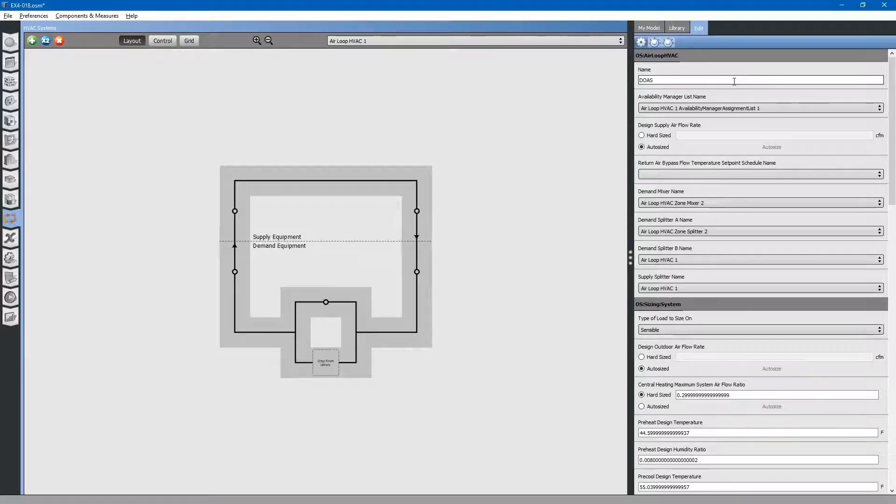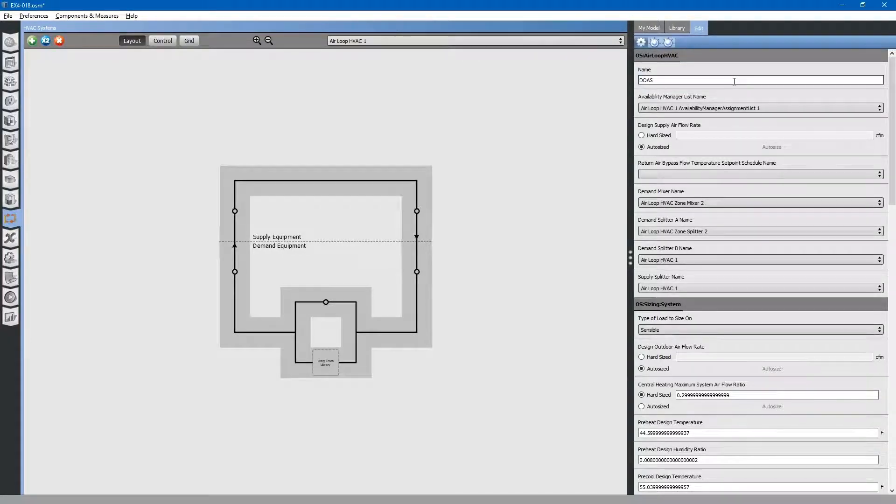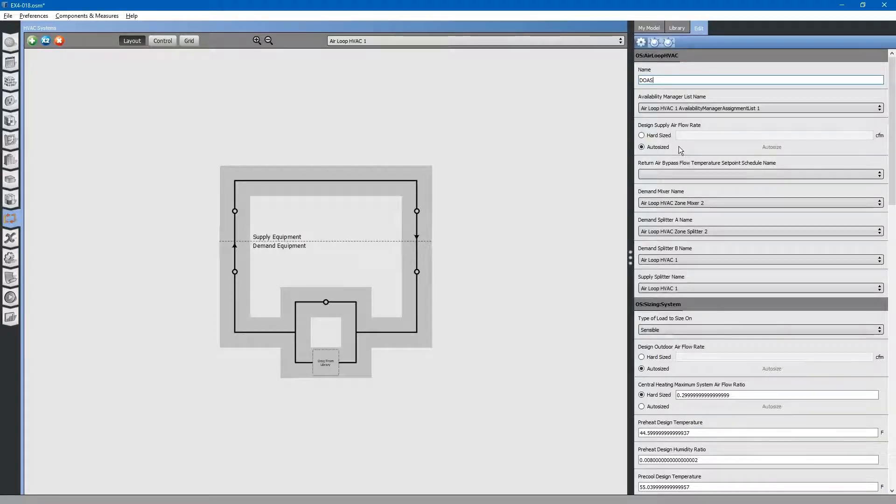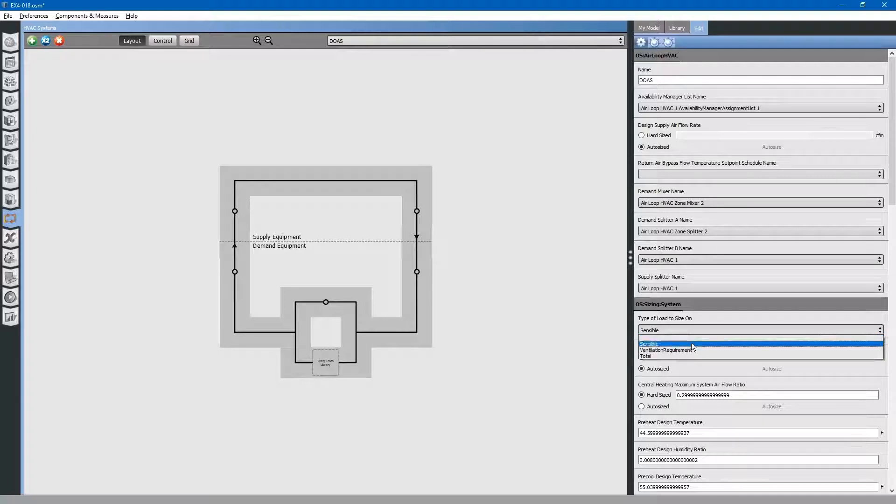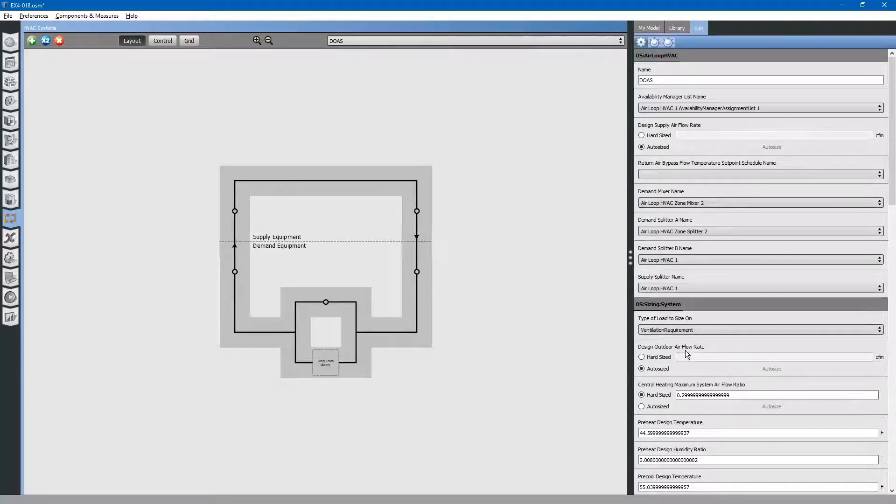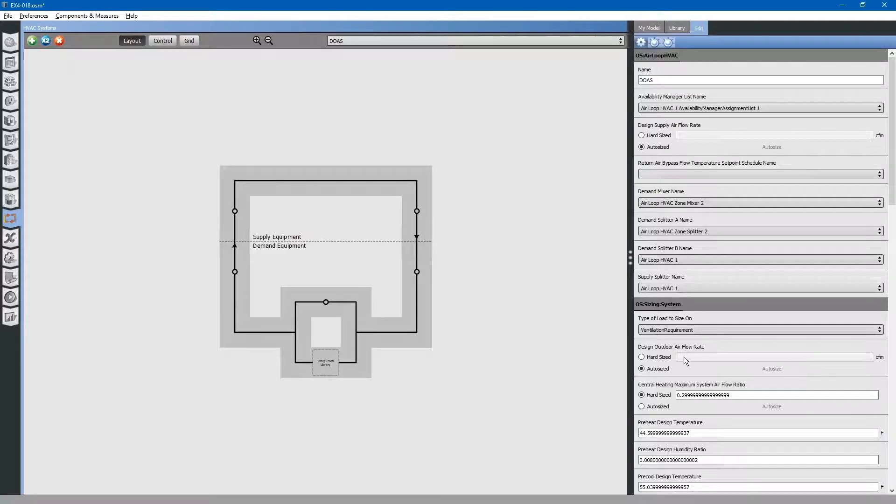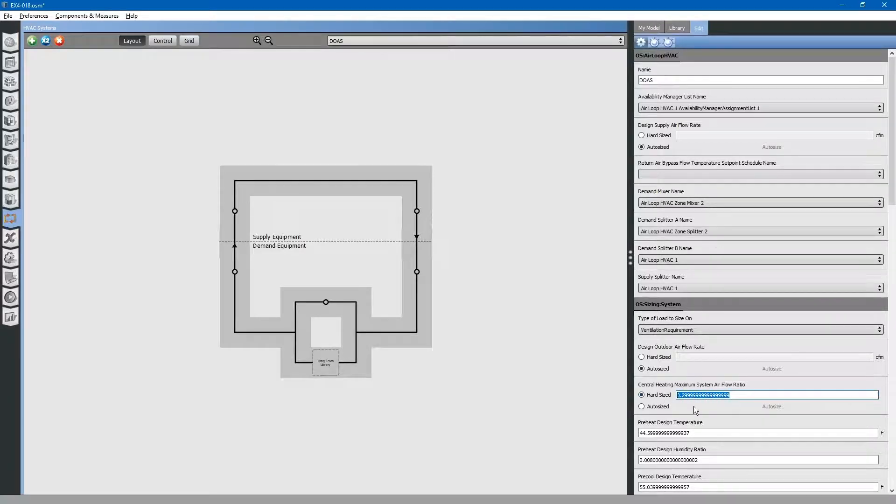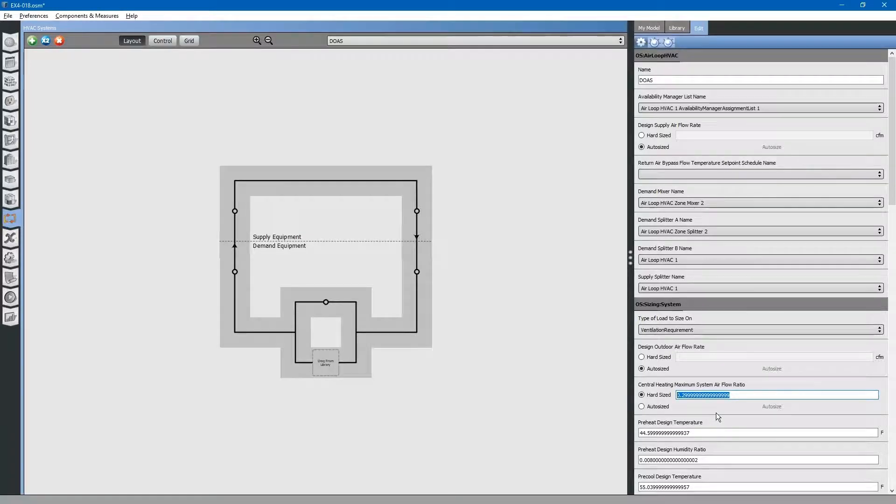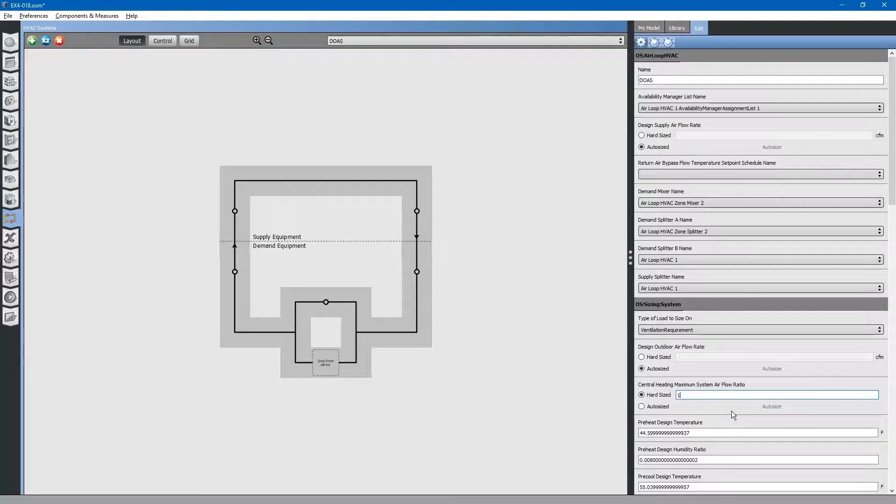We will assign some properties to it. We will allow it to auto size for now. Type of load to size on. This is a dedicated outdoor air system. We will size the system based on ventilation requirement. We will auto size design outdoor air flow rate. Because it is a dedicated outdoor air system, it will be 100% outdoor air. We will have to change this heating maximum system air flow ratio to 1.